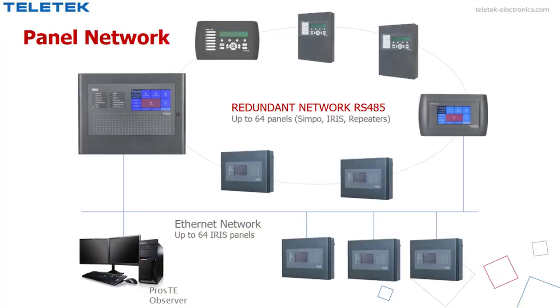It is possible to create a network with up to 64 IRIS, SIMPO and repeater panels. For that purpose, the installers can use two connection methods. Via RS485 redundant network model, you can create a mixed network between IRIS, SIMPO and repeater panels. The second option is to use the built-in LAN modules in the IRIS panels to create a network over LAN.